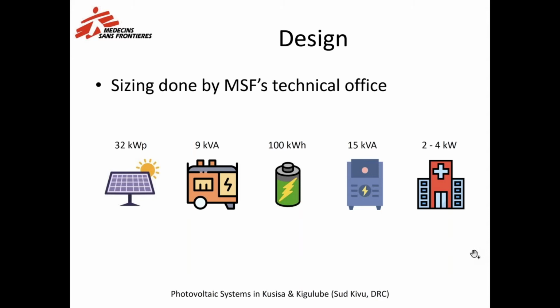The system was designed to work with at least 2 days of low solar irradiance. We are speaking about an area in the middle of the mountains, with long periods of rain, so we wanted to have this autonomy. This is one of the reasons we oversized the solar array. If we had done this system in another place, the solar array might have been a bit smaller, I guess.